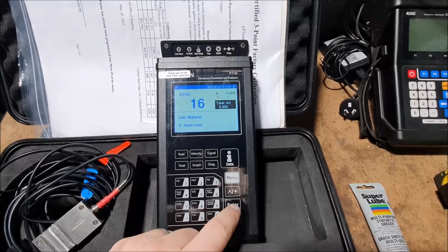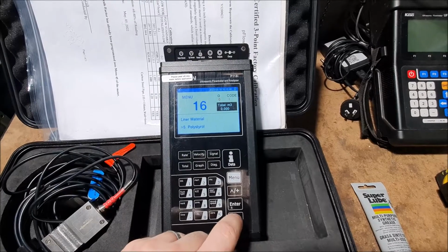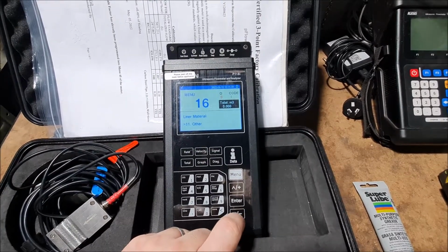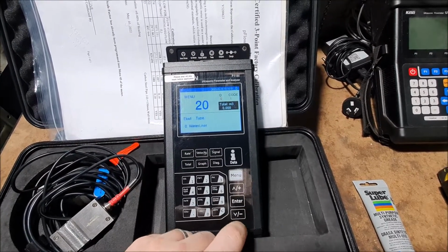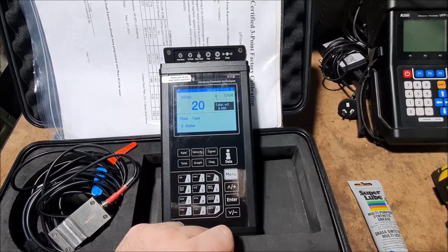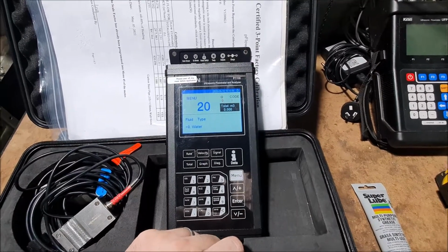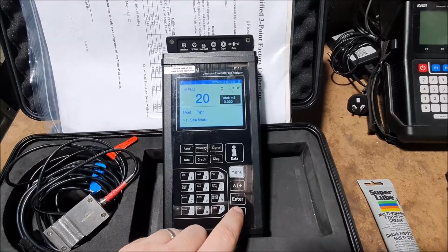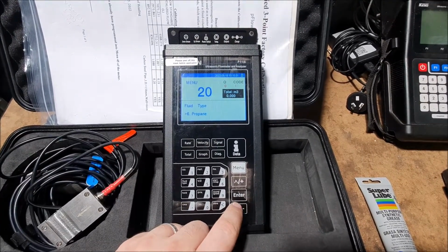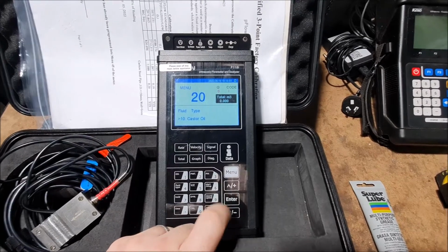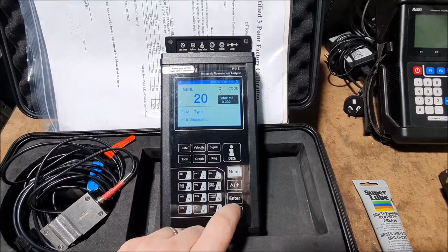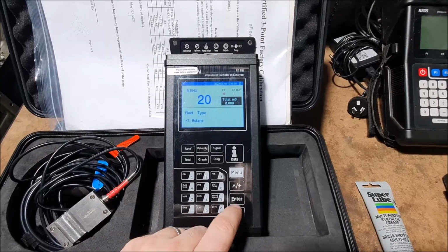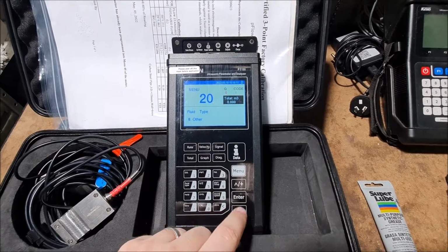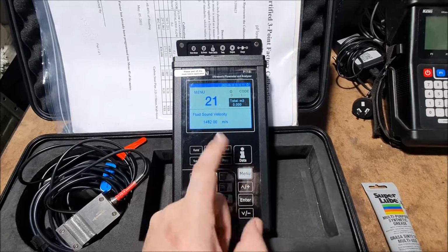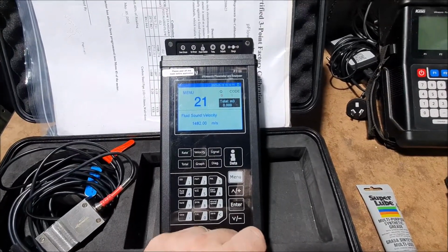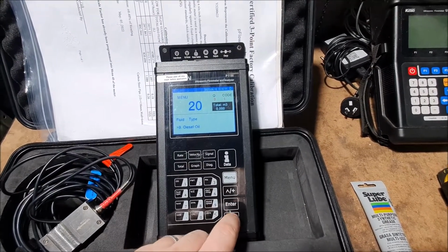If you have a liner, again, it's just the same process. Just enter your liner material here. In this case, we don't have one, so I'll select none. Your fluid. Again, this is just by a selectable list. In this case, I do have water, but you can just press enter, scroll through a list of some common fluids. And again, if your fluid isn't listed here, you can select other. And then the next menu, you can manually enter the sound velocity of your liquid. But in this case, I'm just going to select water.